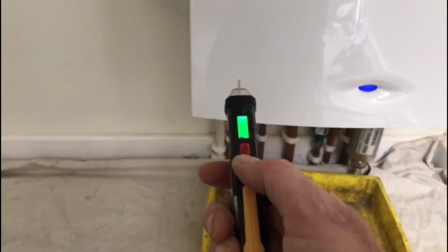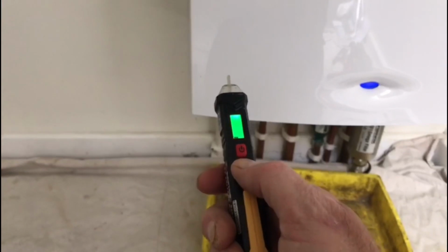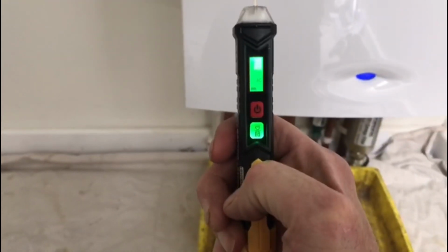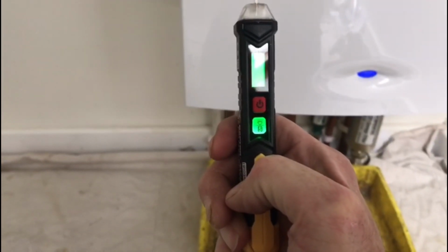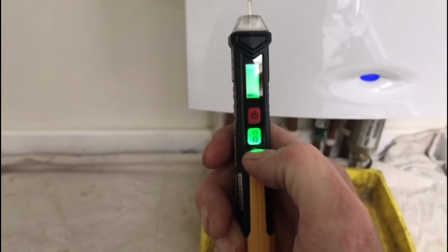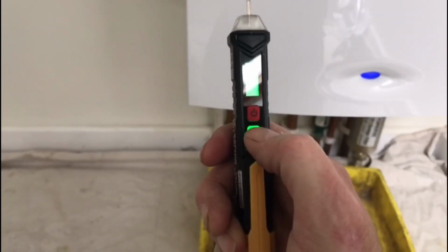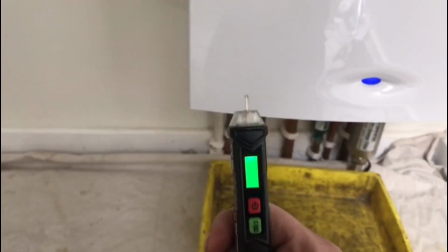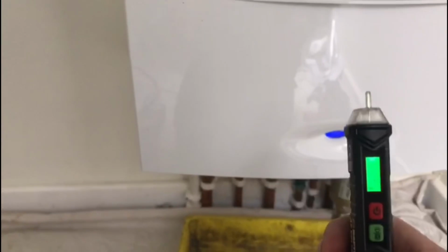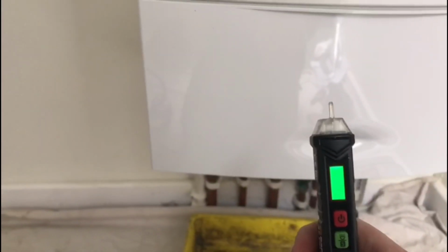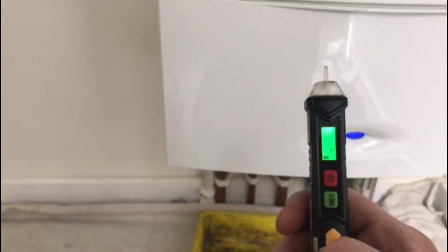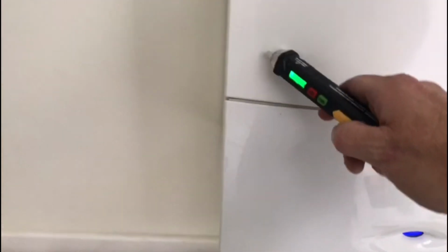If you press the green button once, it goes on to a sensitive reading, so you can use it for more low voltage testing. But for this purpose, just go on to normal non-contact voltage detection. And basically, you've never seen this boiler before, never touched it before. Don't touch it. Use a non-contact voltage detector. Check all the way around the case.